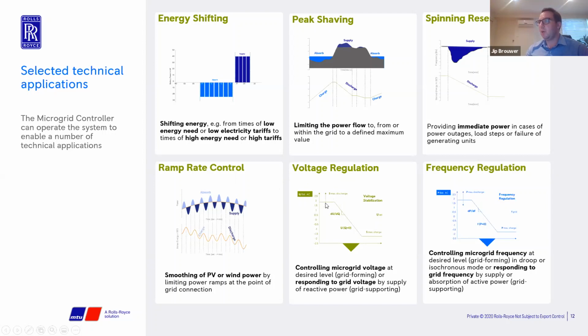Then you have voltage regulation, which usually takes place on a smaller, local network scale, where due to rooftop solar the voltage significantly increases and makes the local grid unstable, potentially damaging various components. The battery can either supply reactive power or control the voltage on that microgrid.